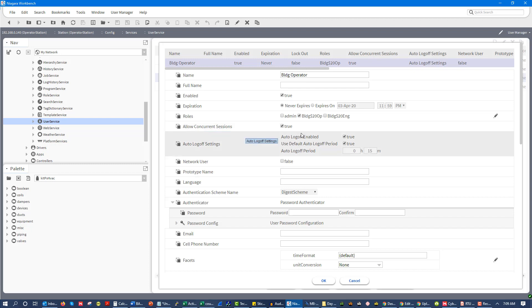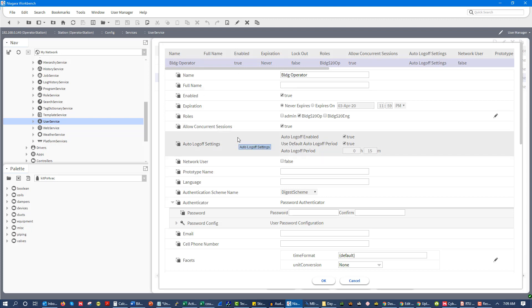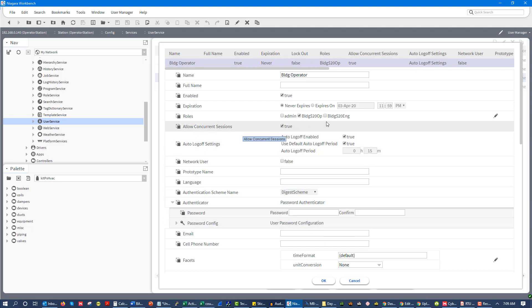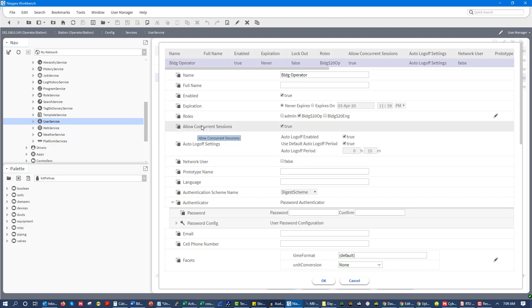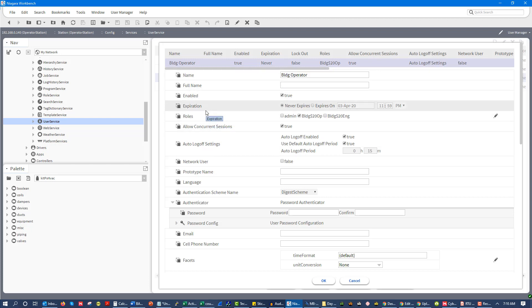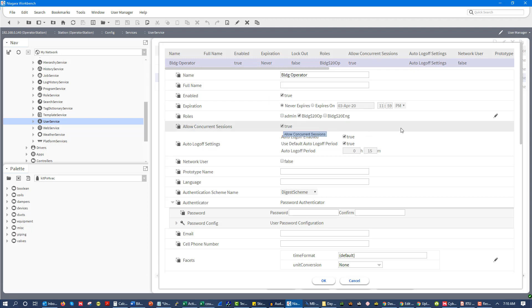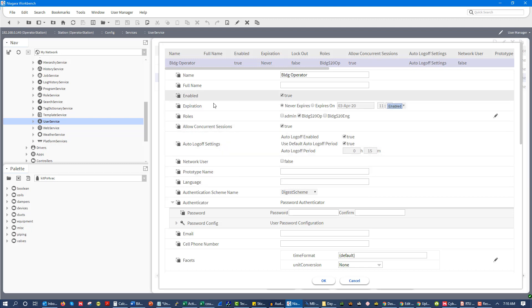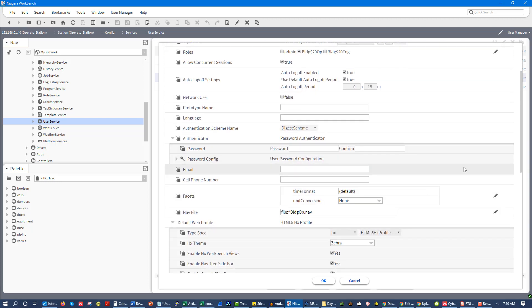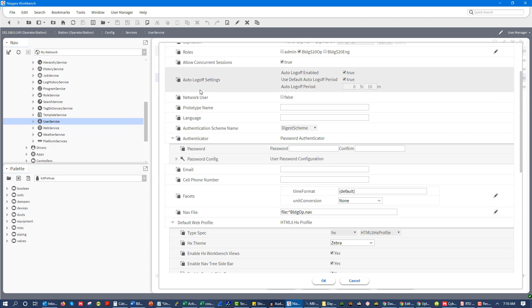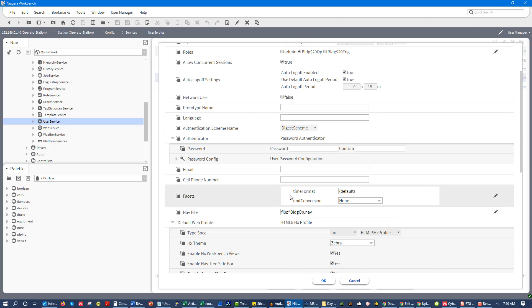One of the really important things from a cybersecurity perspective is that each person has their own account. One of the worst things you can do is having a building operator account that everyone uses. This provides very limited auditing capabilities, and auditing is where you basically log what the role or user is doing. If everyone's using the same account, then you have an issue. Also, if someone leaves the company, you have an issue because that person who left may still have access. Historically, I've seen companies not really change their user profiles and passwords. Other issues include not having expirations on user accounts, not having strong password requirements, not enforcing logout times, not enforcing automatic logout. These are all things from a cybersecurity perspective that are really important.